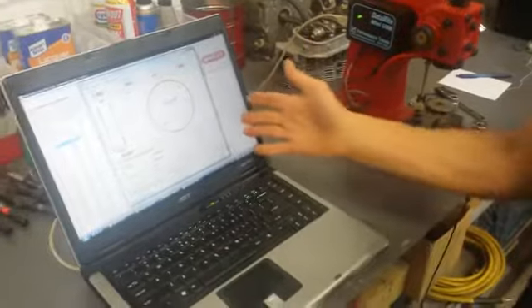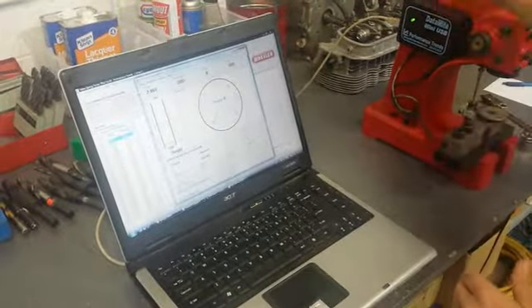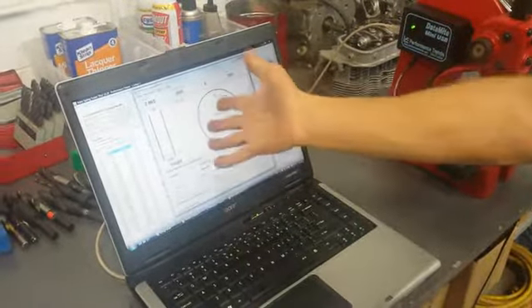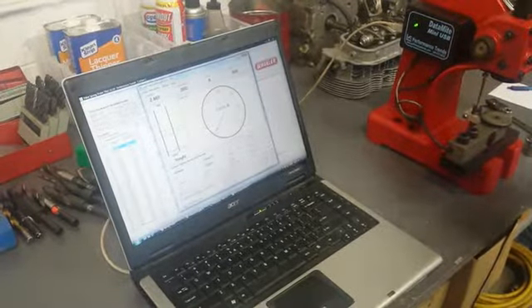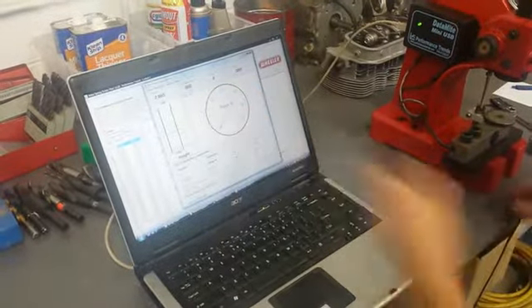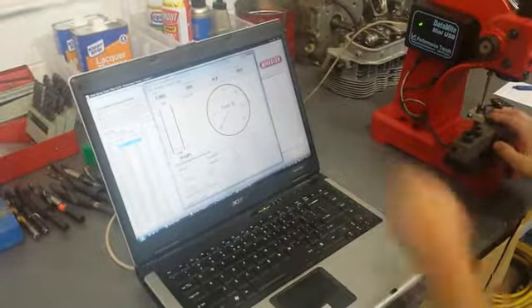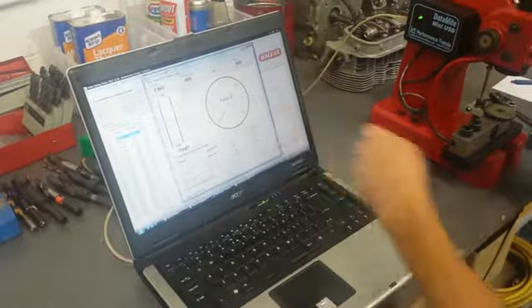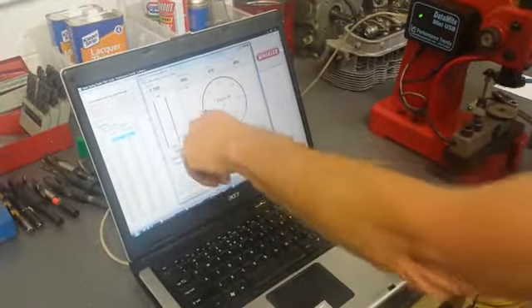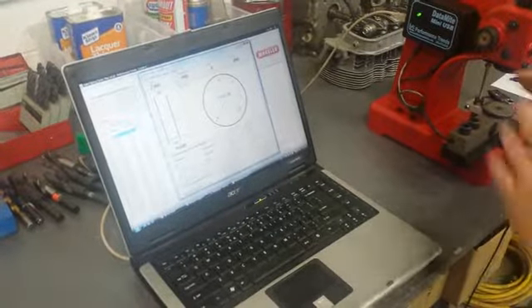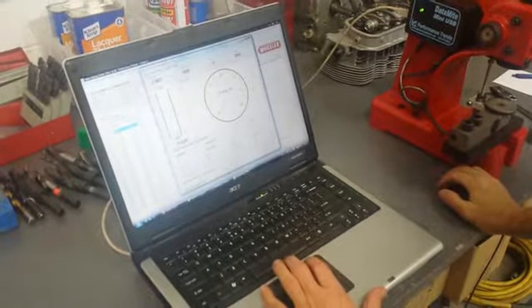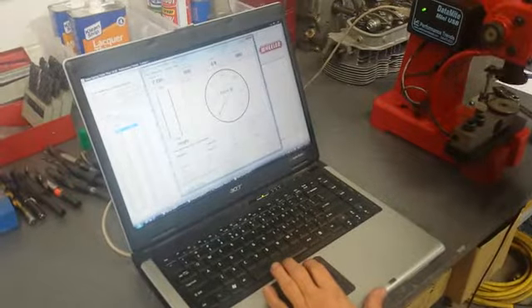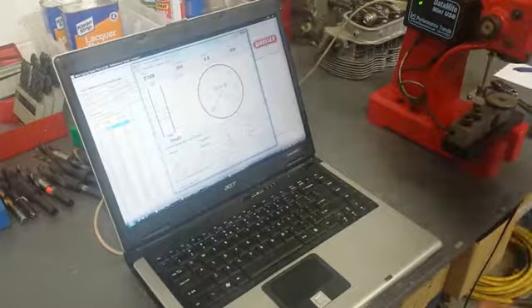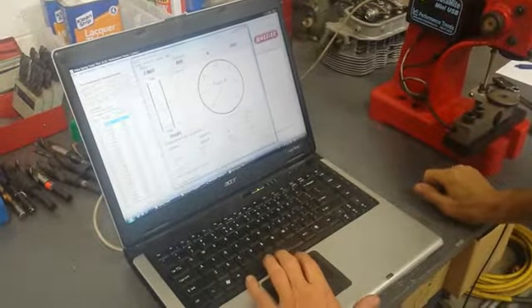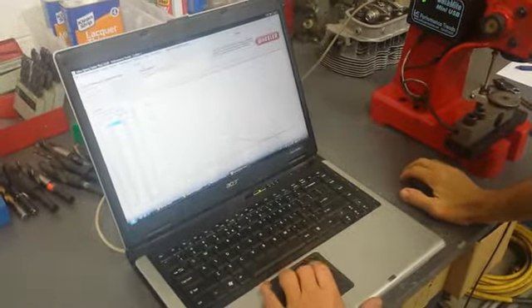So the first thing you want to do, especially if you first got your data logger, is make sure that the Datamite is communicating with your computer. And here we've got it communicating. You see the numbers are changing a little bit, and if I push down on the force sensor, the load cell, you would get a reading. If I go like this on the length sensor, you can see my length sensor is changing. So we've got good communications. The problem might be, when this thing says that it's 2 inches, is it really 2 inches in here? So the process of calibration will make sure that is accurate.